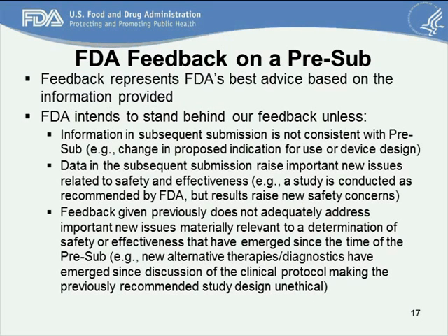The feedback that FDA provides on a pre-sub will represent FDA's best advice based on the information provided. This was discussed extensively during the MDUFA 3 negotiations, and FDA committed in MDUFA 3 to stand behind our feedback unless information in subsequent submissions is not consistent with the pre-sub. So if you've changed your indications for use or made a significant design change, then our previous feedback might not still hold.